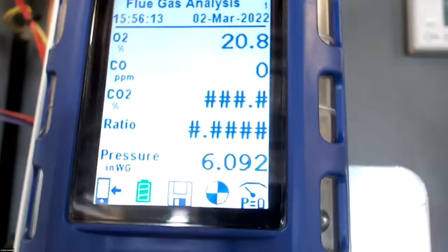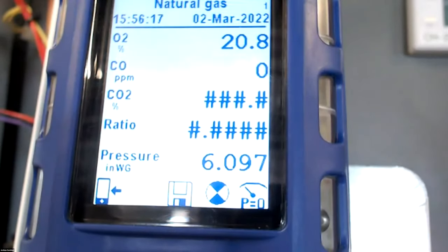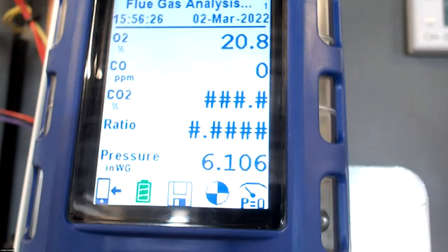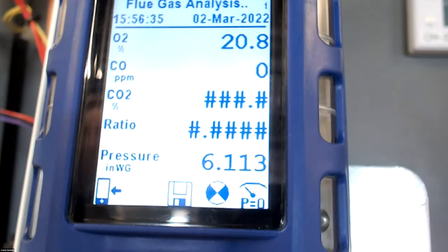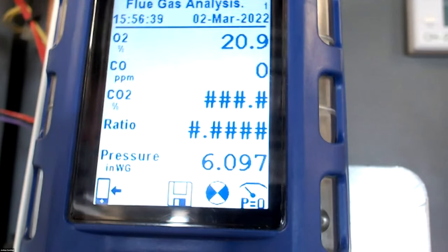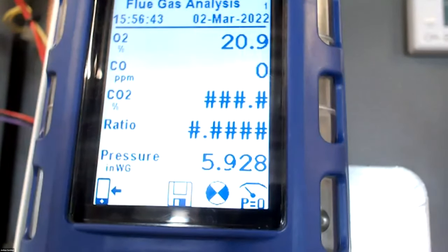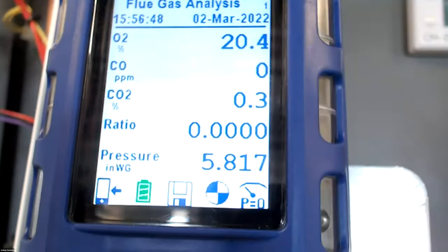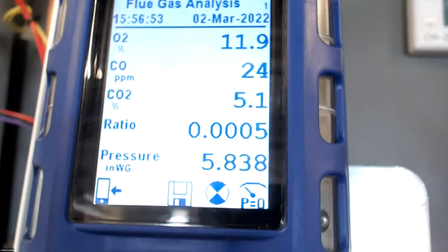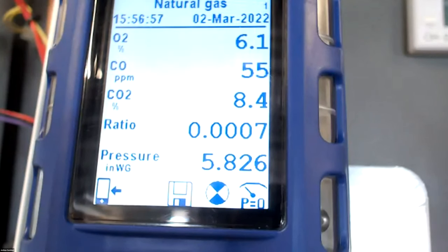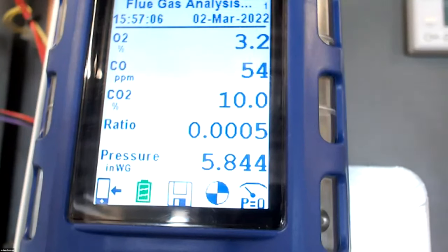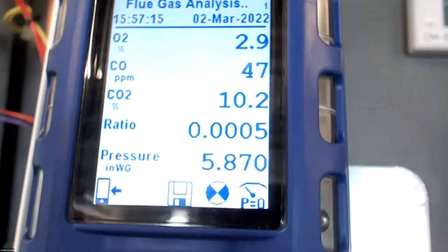All right. So we're going to look at the low fire now. Go back in, turn everything off. Go back into our installer settings. All right, we're fired off, analyzer is doing its thing. So we set this up with that throttle in high fire, then we bring it down to low fire, and the majority of the time it's right in there, within our parameters. And then we're done, we walk away. That's commissioned. We take a picture of that low fire and we're good.